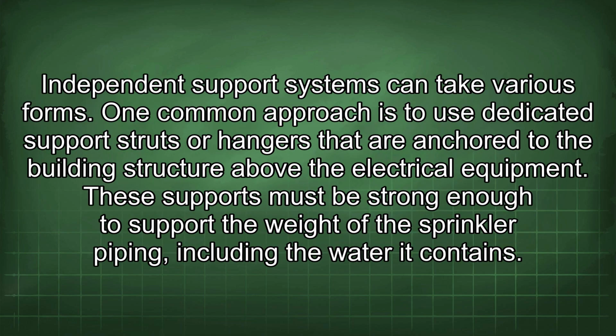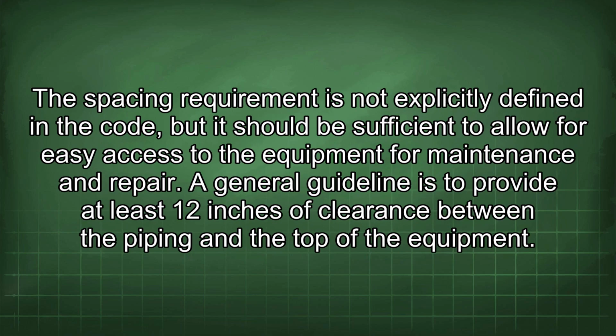Independent support systems can take various forms. One common approach is to use dedicated support struts or hangers that are anchored to the building structure above the electrical equipment. These supports must be strong enough to support the weight of the sprinkler piping, including the water it contains. The spacing requirement is not explicitly defined in the code, but it should be sufficient to allow for easy access to the equipment for maintenance and repair.